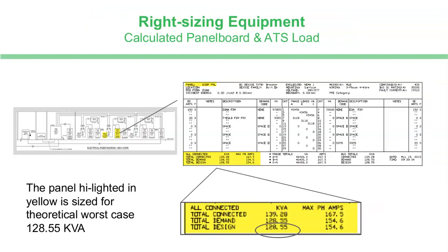A little bit of explanation. This is an example of an existing panel and whether or not you have to make it larger or make a change. On new equipment, you would always follow NEC procedures and methods for calculating load. But where you've got existing circuits, using existing data is not only good, it's recommended.